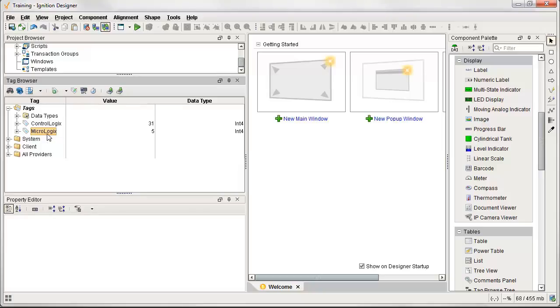That's not a problem. The problem happens when I want to write a value to a specific bit of a word. If I leave it as an integer here, I'd have to somehow mask out that write and hope that only that one bit is what I'm changing when I write that down to the PLC. So with Ignition, you have to create a separate tag for every bit you want to write down to. So it's really easy to actually address a bit.